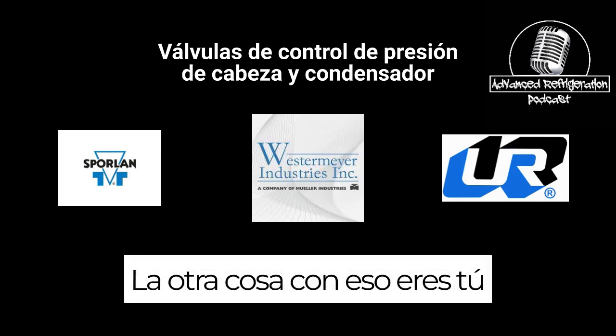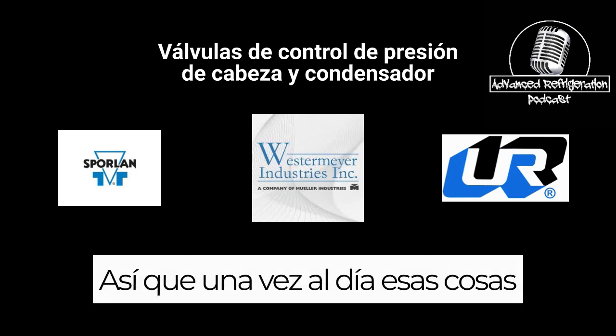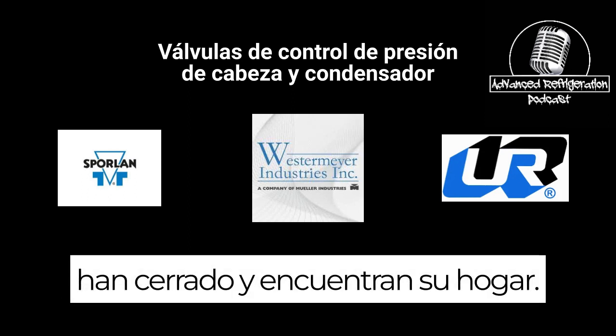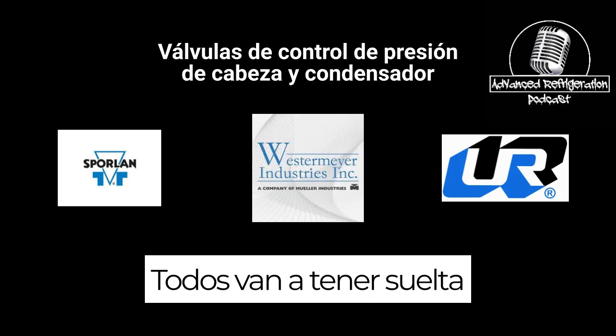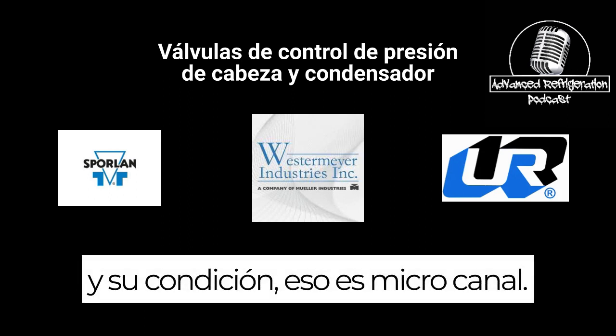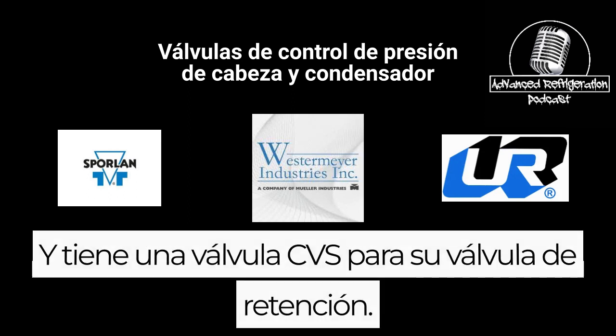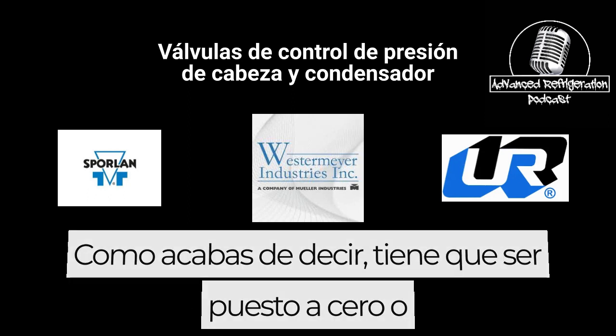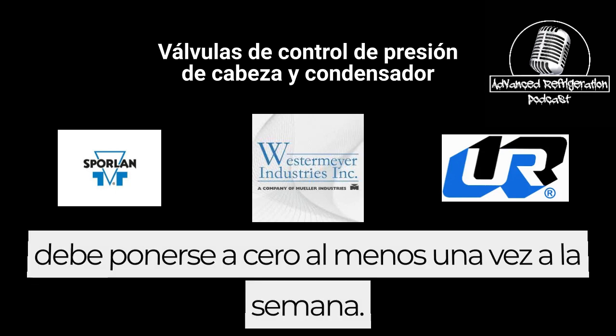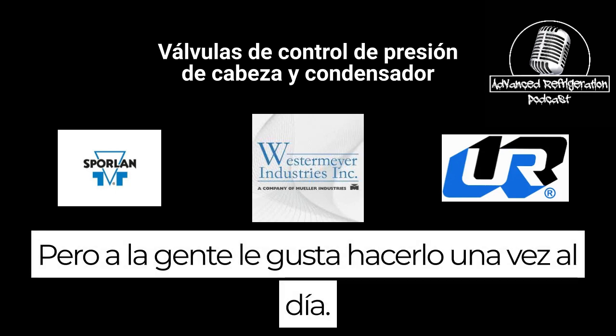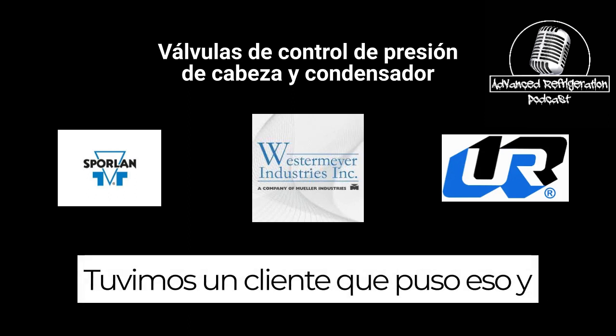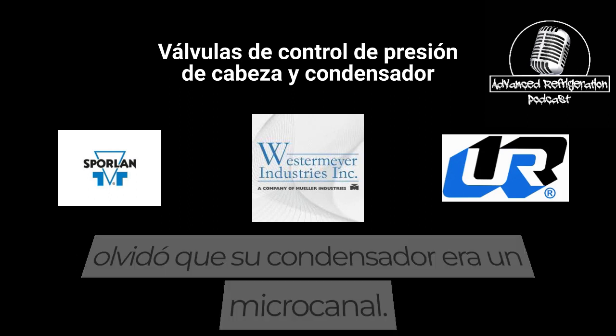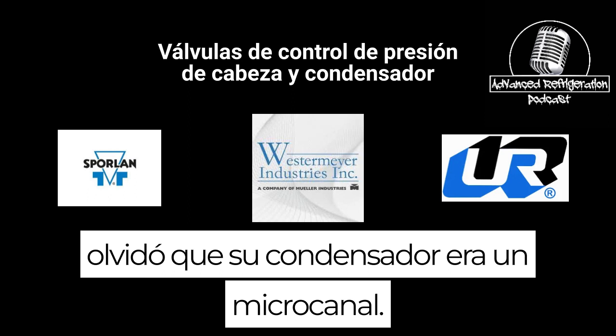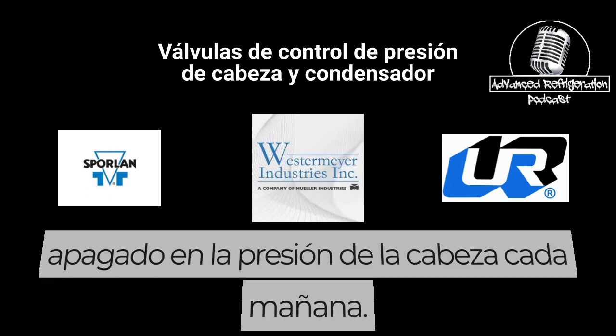The other thing with that is you have to zero those valves out. So once a day, those things have to close and find their home. They're also going to have a condenser that's microchannel, and you have a CDS valve for your holdback valve. Like you just said, it has to be zeroed out, or it should be zeroed out at least once a week. But people like to do it once a day.